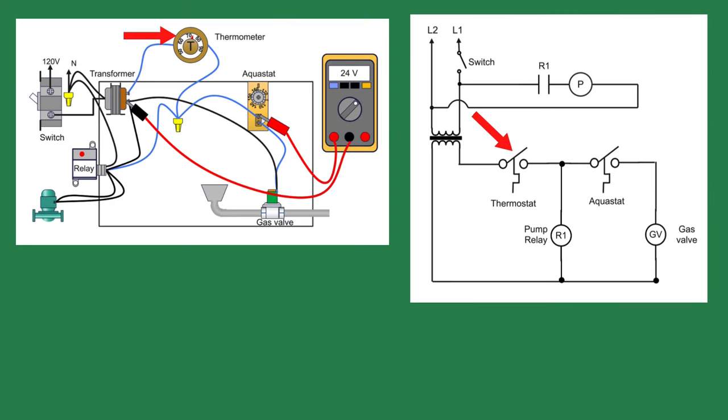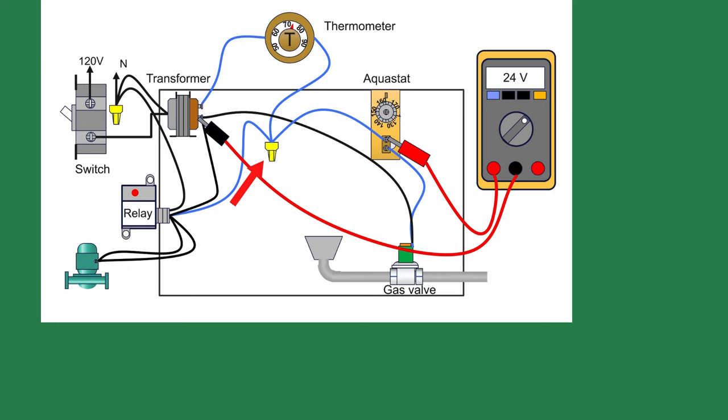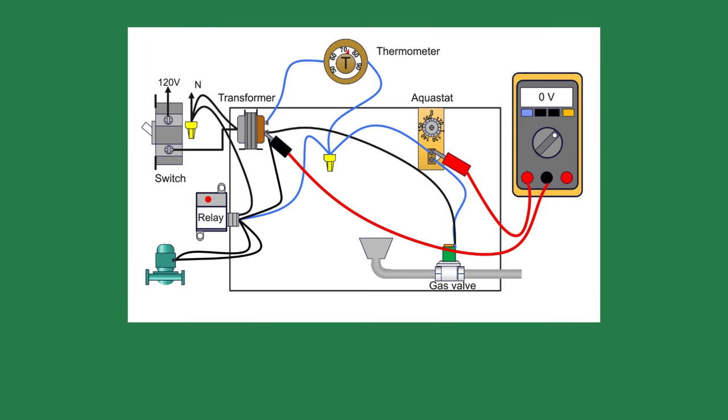The 24 volts leaves the transformer and goes to the thermostat. If the room temperature is lower than the thermostat set point, we should have power returning from the thermostat and could verify that by touching one meter lead on the incoming terminal of the aquastat and the other to the neutral terminal on the transformer. You could also insert the meter probe into the yellow wire nut instead of the aquastat control. We know the red light on the relay is not lit, so we know we have no power returning from the thermostat because the same wire from the thermostat feeds the coil on the relay.